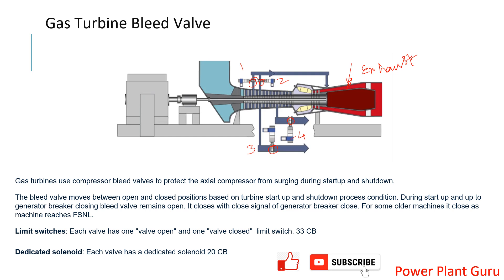Why is this kind of system there? There is a thing called compressor surge. Very briefly: let's say there is some inlet pressure and a discharge pressure P2, but if you are not able to have a proper exit of gases at the exhaust side — for example, the machine is running and there is a sudden blockage or very low opening at the exit — there will be a sudden pressure rise.